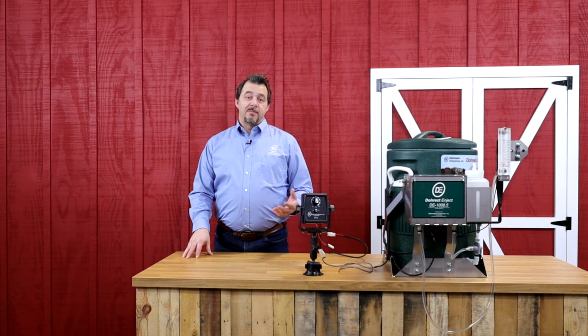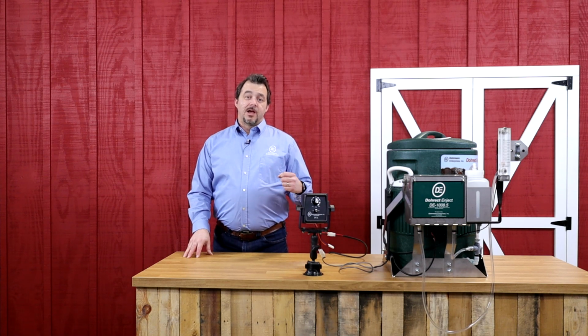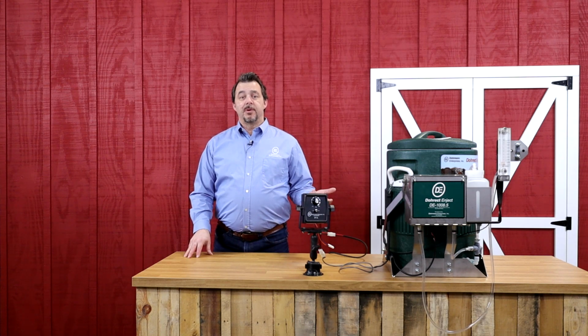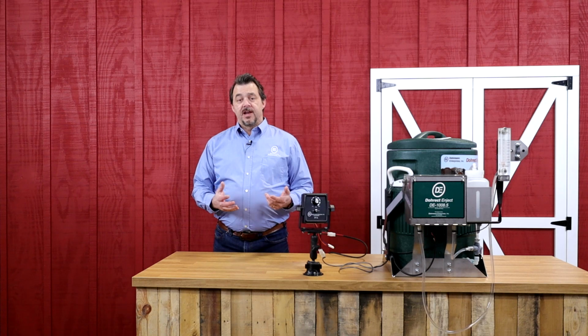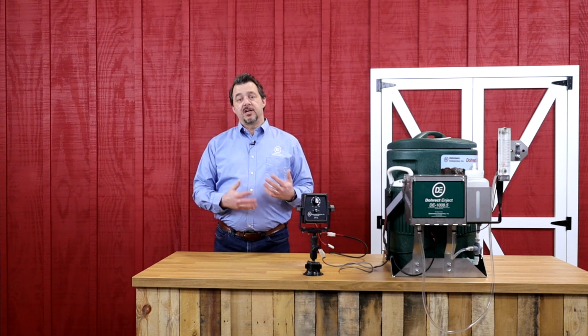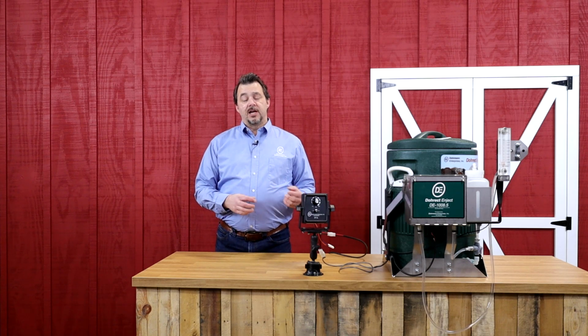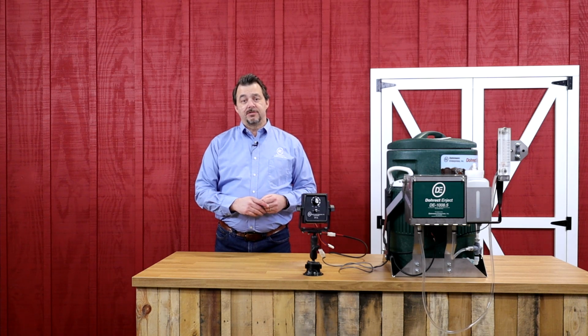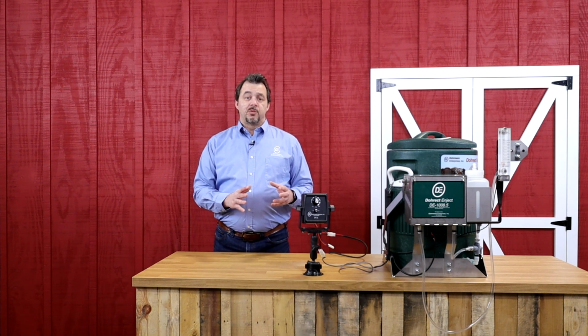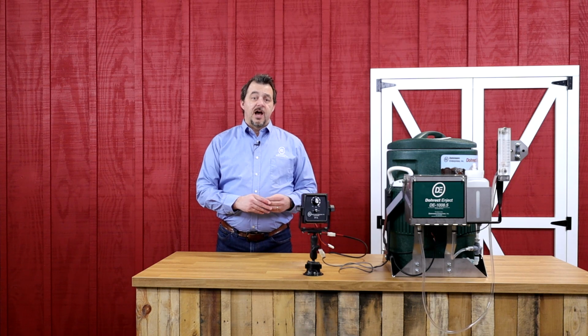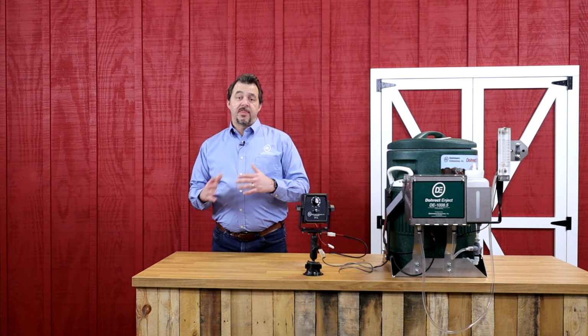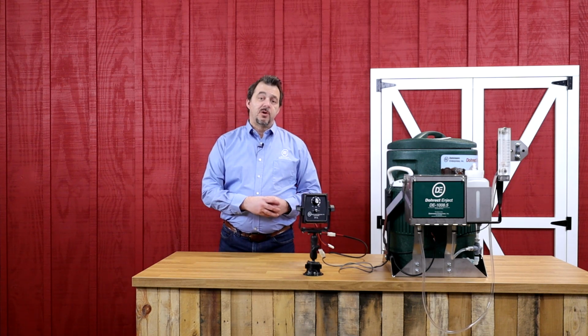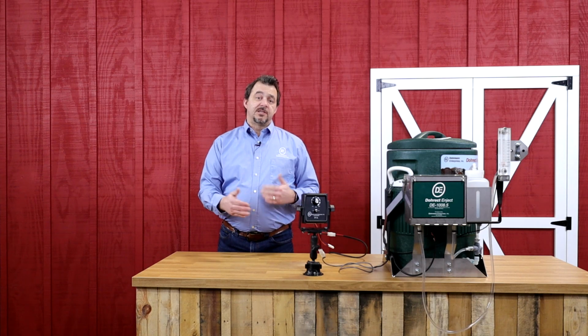Now, admittedly, this video might be a little backwards, because obviously you have to make sure that your pump is running before you can worry about it actually pumping. But more often than not, with troubleshooting these systems, we take calls with regards to pumping, so we wanted to address that in the first half. If you are in a situation where your motor does not run, we will have to work through that and then go back to the beginning of the video in the event your system is not pumping after we get everything up and running.